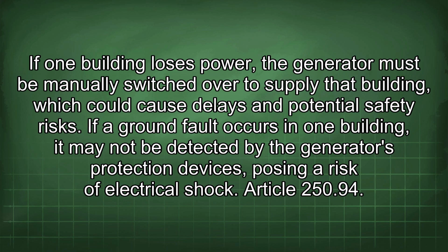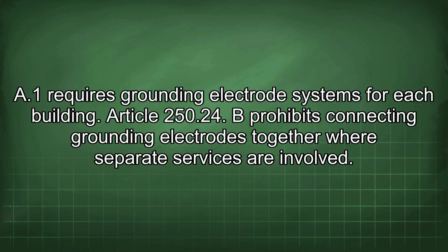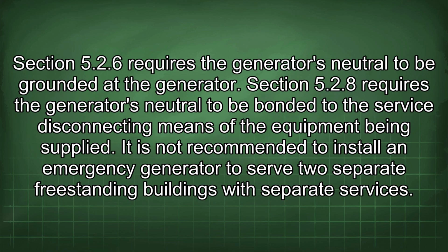Article 250.94 A1 requires grounding electrode systems for each building. Article 250.24 B prohibits connecting grounding electrodes together where separate services are involved. Section 5.26 requires the generator's neutral to be grounded at the generator. Section 5.28 requires the generator's neutral to be bonded to the service disconnecting means of the equipment being supplied.